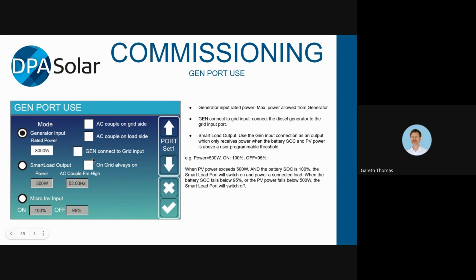Again, connected to grid input. That's this one here. That's basically if you decide for whatever reason to wire the generator into the grid input instead of the generator input, perhaps you might want to use the generator input as a smart load. Then you need to tick this box here. It's still going to limit the charge from that same set of contacts, though, according to what you've put under the grid settings in the battery menu. Does that make sense? Does that make sense to you, David? Mm-hmm. Yep. Okay. So even though you've told it that the generator is on the grid input, when you're changing that maximum grid charge current value in the battery settings, you need to change it on grid, not on generator.